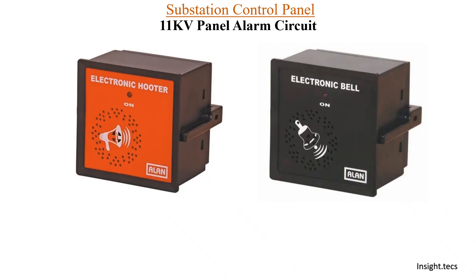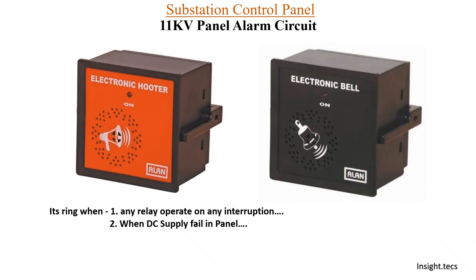This kind of electronic hooter is available right now in the panel. So this is an electronic hooter — or you can call it an electronic bell. It rings when any relay operates on any interruption; basically in case of any tripping, this will be operated. Second, when there is a DC supply fail in the panel, again you will hear this. And when there is AC supply fail in the panel, you can hear this electronic hooter.